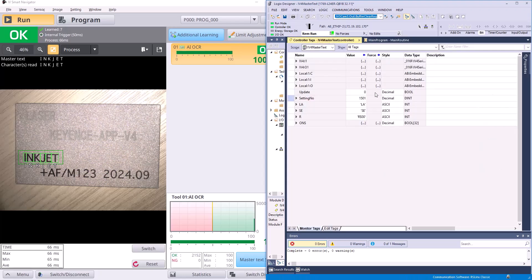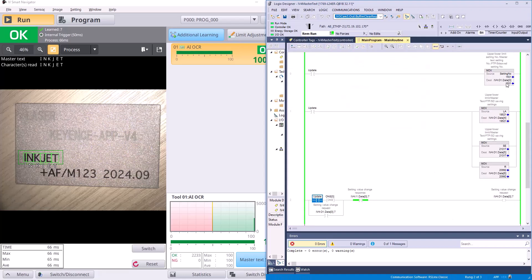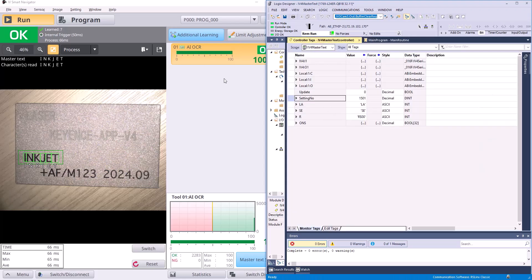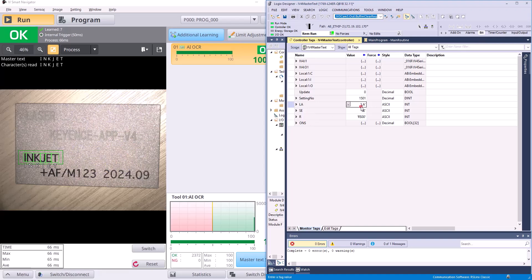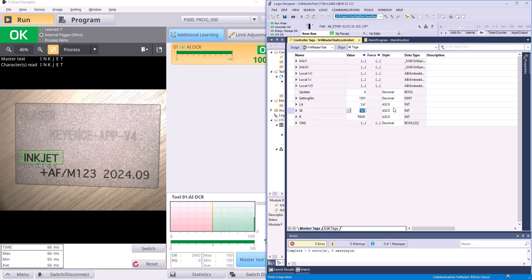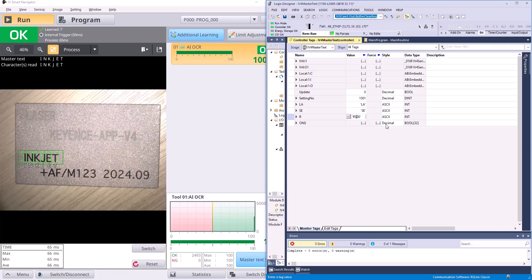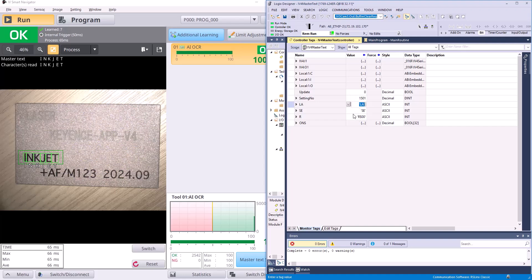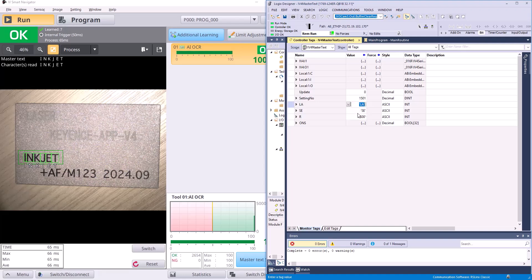I've got my setting number, which is 1501. Now 1501 is the specific number you have to write to the IV4 at our output data 3 in order to make sure that it updates all the letters in a batch. So 1501 is the number to look for here. I've got LA, SE, and R here just as ints. And I've just got them formatted so their style is ASCII. And you'll see at the end of the R one we have $00 and this is the ASCII character for null. Whenever you send the master text to update it and you're sending that to the IV4, you have to make sure it ends with the null character just so that the IV4 knows the text it's receiving is done.